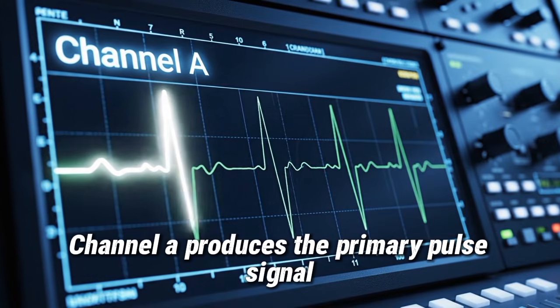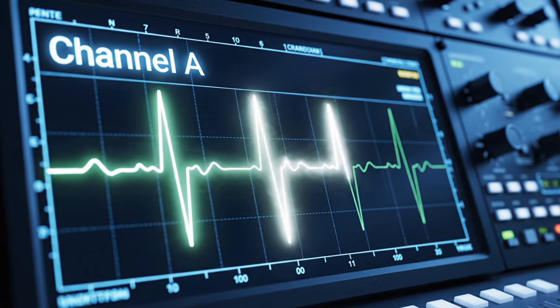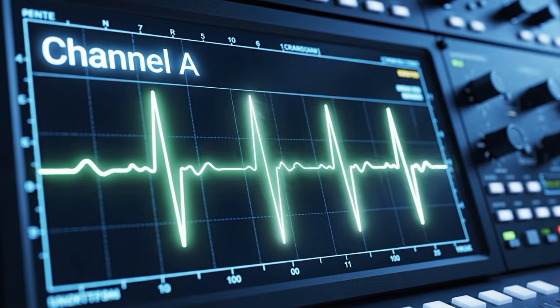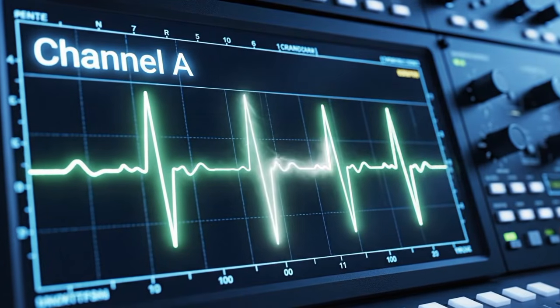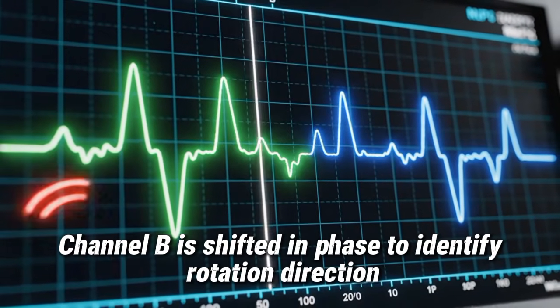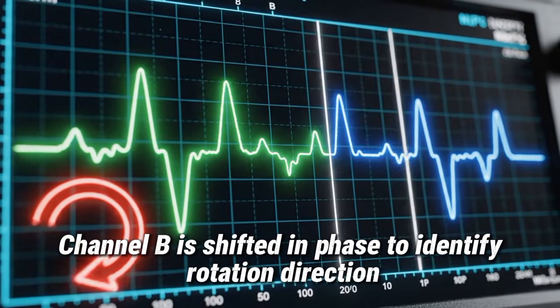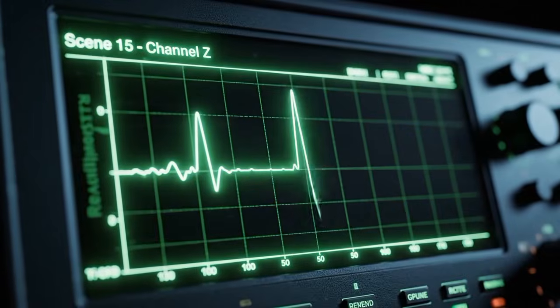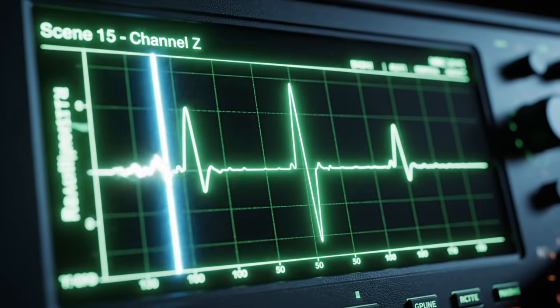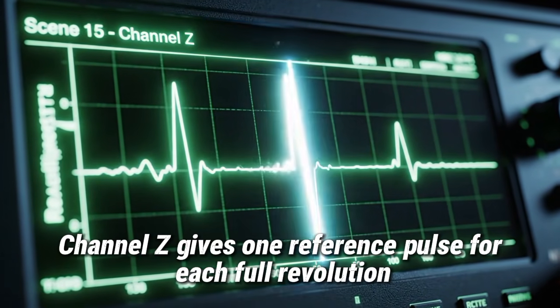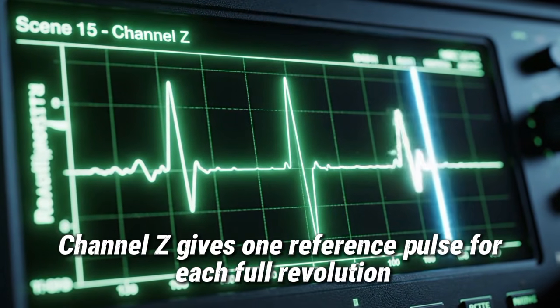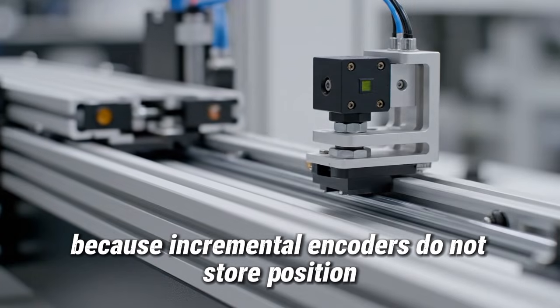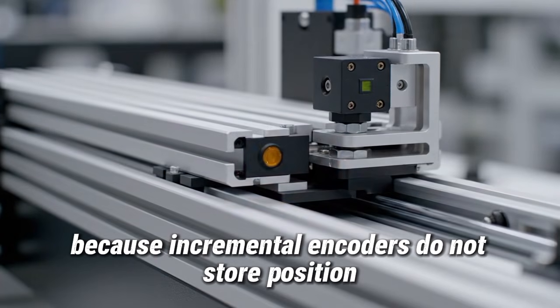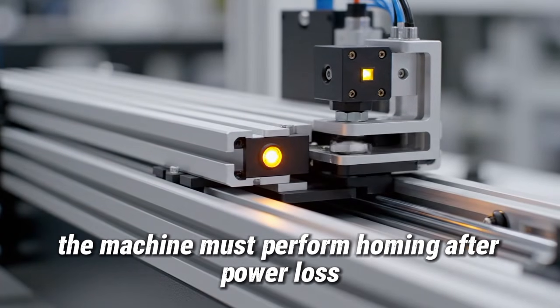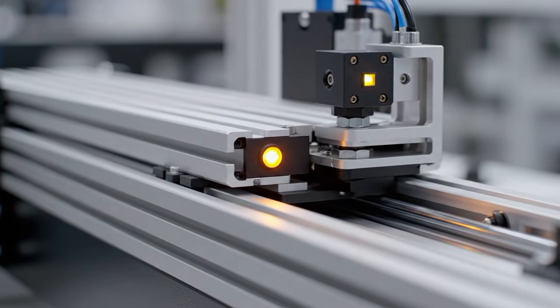Channel A produces the primary pulse signal. Channel B is shifted in phase to identify rotation direction. Channel Z gives one reference pulse for each full revolution. Because incremental encoders do not store position, the machine must perform homing after power loss.